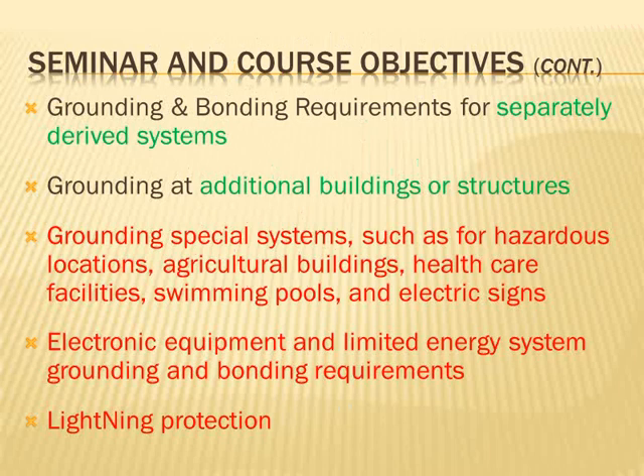So long story short, as far as we're concerned, the grounding system for the lightning system has to be bonded completely with our system. So you find if they have multiple rods, that's why in bigger buildings, we end up having 500 kcm conductor, because 500 kcm conductor tying, instead of 4-aught to a 3-aught per the code, tying it to the ground bar, because you have electronics to ground, you have lightning to take care of, and you have the power system to take care of. So you end up with a bigger conductor. So just be aware of that. If you see a 500 kcm conductor tied to the steel of a building, they're taking into consideration lightning, they're taking into consideration electronics, and they're taking into consideration the power system. So keep this in mind.